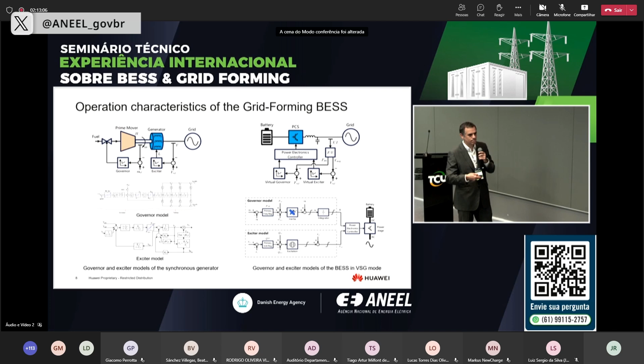This is one screenshot of the main functionalities in the state-of-the-art grid forming BESS. And we can see that in case of fault, the black one is the traditional solution, providing a little bit of short circuit contribution, but the grid forming, the top grid forming, can provide up to 2 times, 3 times short circuit current. That will be very useful, for example, for the protection system, detecting faults, isolating the fault, etc., or for energizing induction motors. In case of fault, the induction motor will require a lot of reactive power for energizing again. No? So that's why this functionality is very useful.